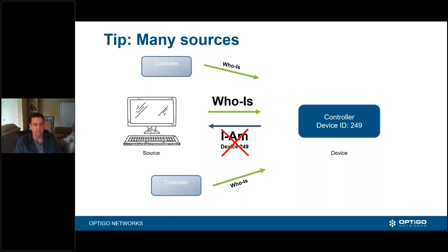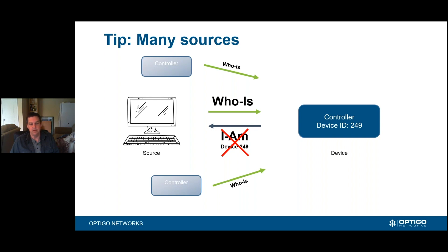There's also another case where there's more than one source sending out too many requests and the poor device just can't respond. Before we had servers, we used to have just BACnet clients, and that's still out there today — multiple front ends all asking who-is requests for the same device. Maybe that device is getting overwhelmed and can't respond to all the requests. If you're seeing some unresponsive devices every now and then, it's possibly because that end device cannot deal with the amount of traffic coming into it.